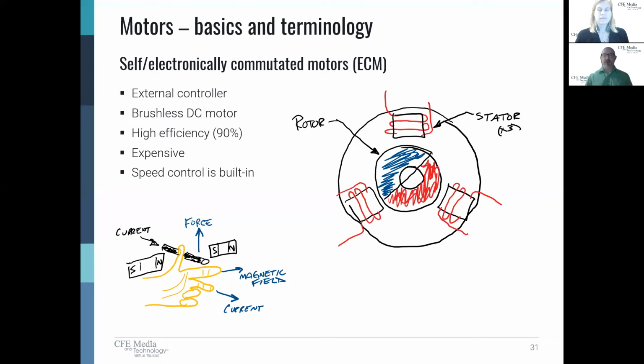Now, this is going to be a push, pull effect. So I'm going to push the motor away, because if I take a north pole and a north pole and try to push them together, they're going to repel. If I do a north pole and a south pole of a motor, they're going to attract. Well, I can generate these magnetic fields. So that's what an ECM does, is I can have 3, 6, 8, 10, 12, as many of the external stator windings as I want, to basically think of a spinning top that you just keep pushing and tapping with your finger. You can get the motor started, and you can actually run at very high speeds. So it's important to understand that magnetic fields are going to be manipulated in a DC motor and generated through coils and windings, unlike an AC motor, which we're going to look at next.